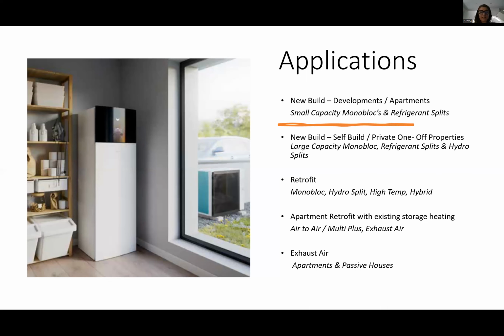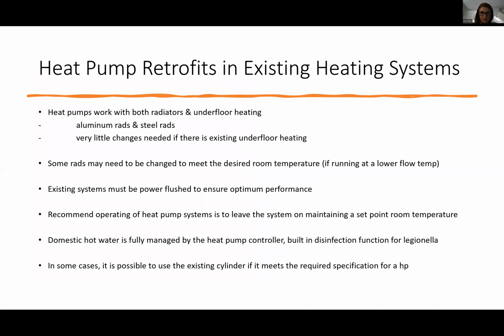So just to give you an idea of how heat pumps fit into existing properties with existing heating systems, they work with both radiators and underfloor heating. So if you have underfloor heating in a building, it's really, really easy to retrofit a heat pump. It works really well with underfloor heating because it's already a low temperature heating system. So there isn't a lot of changes that need to be made in the system. If there's radiators, some radiators might need to be changed. You can use aluminium rads and steel rads.